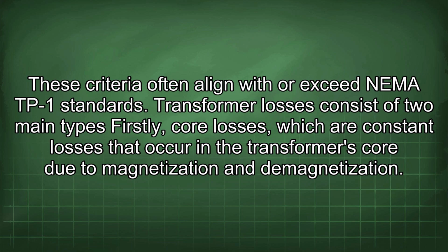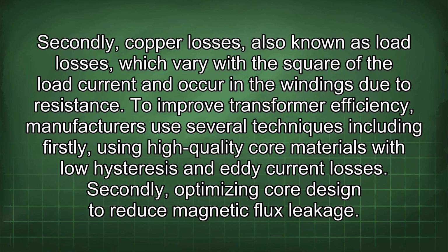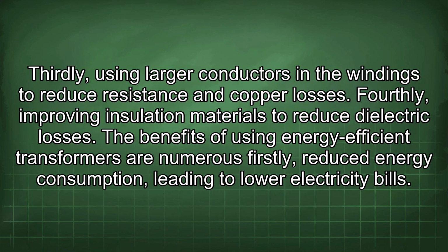Transformer losses consist of two main types. Firstly, core losses, which are constant losses that occur in the transformer's core due to magnetization and demagnetization. Secondly, copper losses, also known as load losses, which vary with the square of the load current and occur in the windings due to resistance. To improve transformer efficiency, manufacturers use several techniques, including, firstly, using high-quality core materials with low hysteresis and eddy current losses. Secondly, optimizing core design to reduce magnetic flux leakage. Thirdly, using larger conductors in the windings to reduce resistance and copper losses. Fourthly, improving insulation materials to reduce dielectric losses.